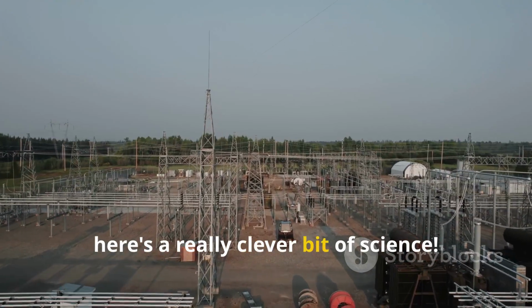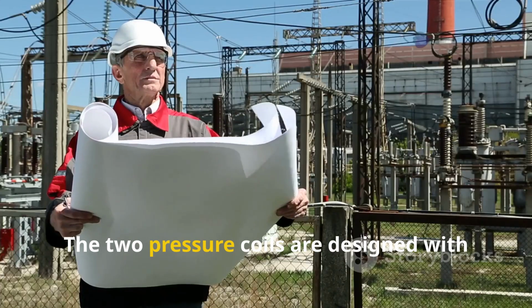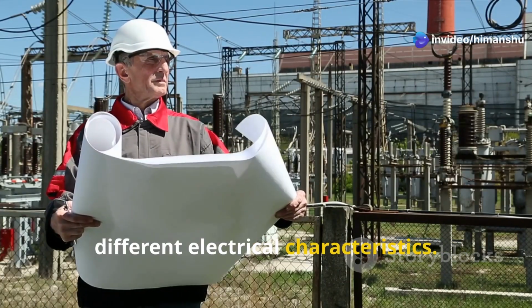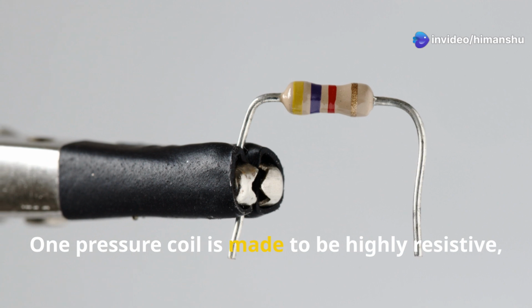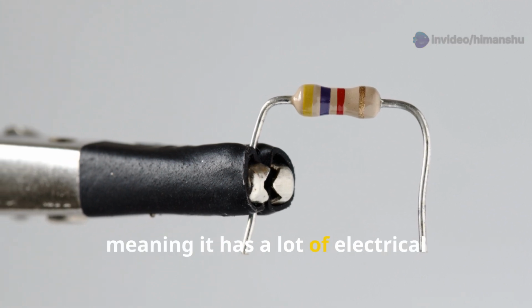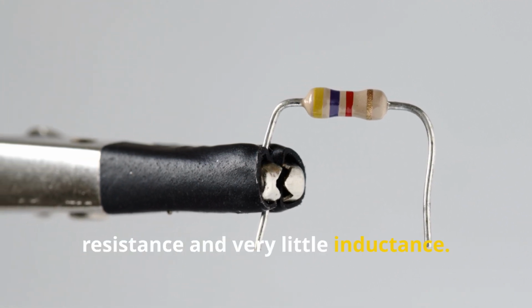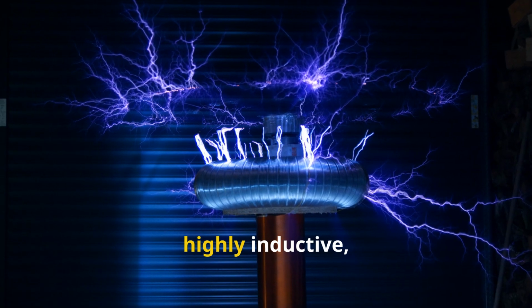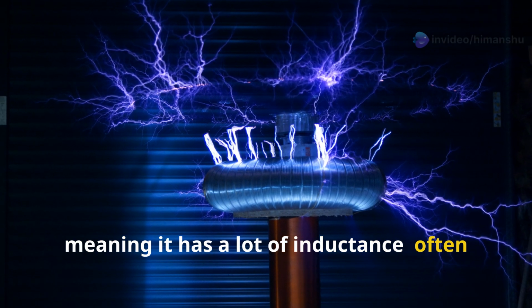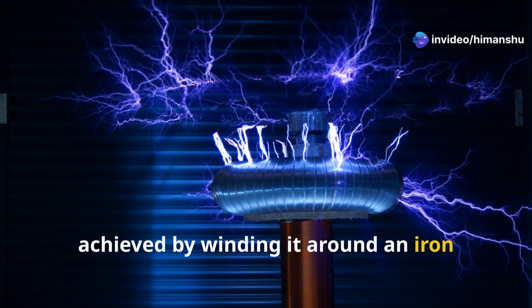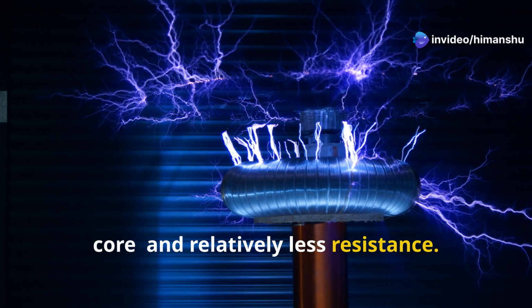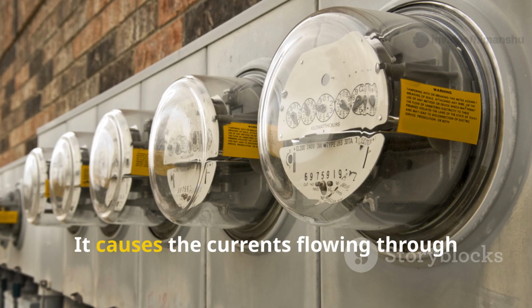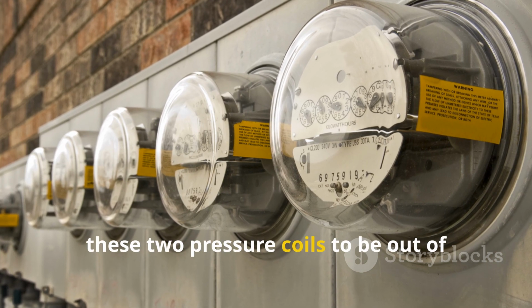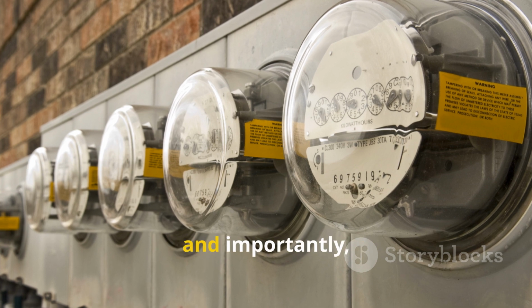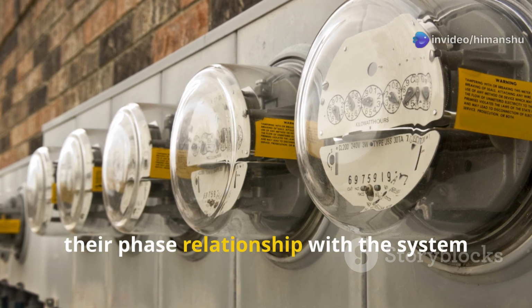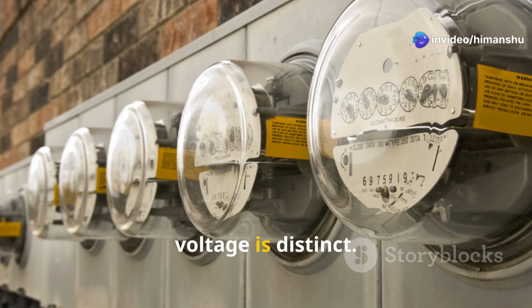Now, here's a really clever bit of science. The two pressure coils are designed with different electrical characteristics. One pressure coil is made to be highly resistive, meaning it has a lot of electrical resistance and very little inductance. The other pressure coil is made to be highly inductive, meaning it has a lot of inductance, often achieved by winding it around an iron core, and relatively less resistance. This difference is key. It causes the currents flowing through these two pressure coils to be out of phase with each other, and importantly, their phase relationship with the system voltage is distinct.